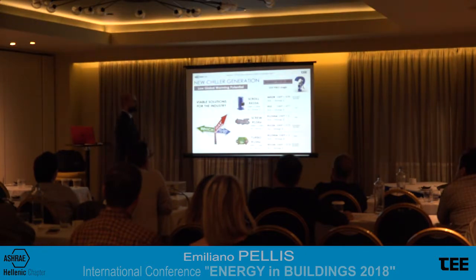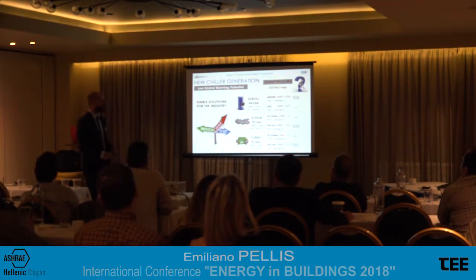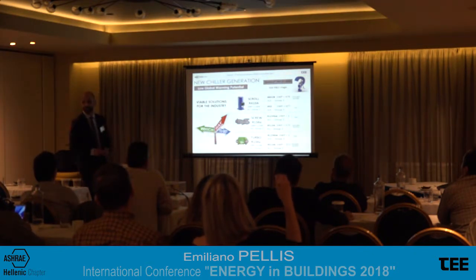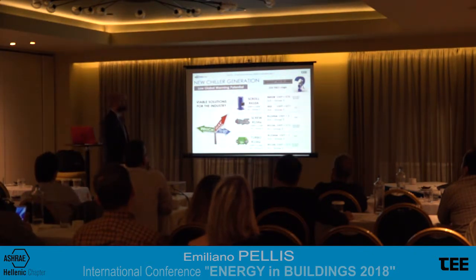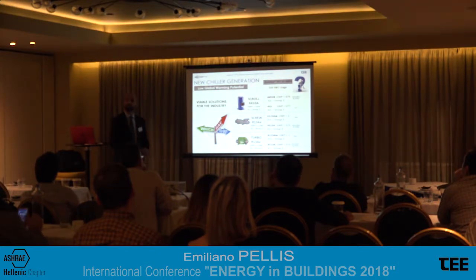What is the other solution? The 1234ze. This is one of the refrigerants belonging to the new family of the HFO, hydrofluoroolefins. Very low GWP, less than 1 according to the ISO classification of refrigerants. But this is A2L, so mildly flammable, and still group 2 of the PED. 513A is a blend of HFO and HFCs.